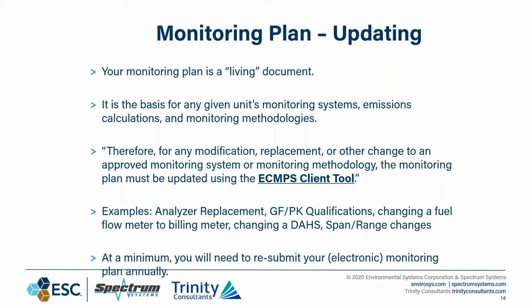Something as simple as an analyzer replacement, changing your qualifications, changing fuel flow methodologies from a certified gas flow meter attached to the unit to a billing meter that was outside the fence, changing a DAS, doing any span or range changes used to take infinitely longer because everything was done as a flat file submission. Having an electronic browser base that allows you to modify, import, and submit ad hoc is a huge time saver by comparison to what it used to be.